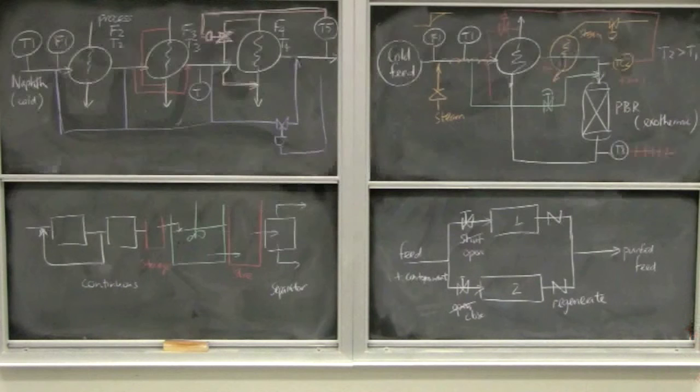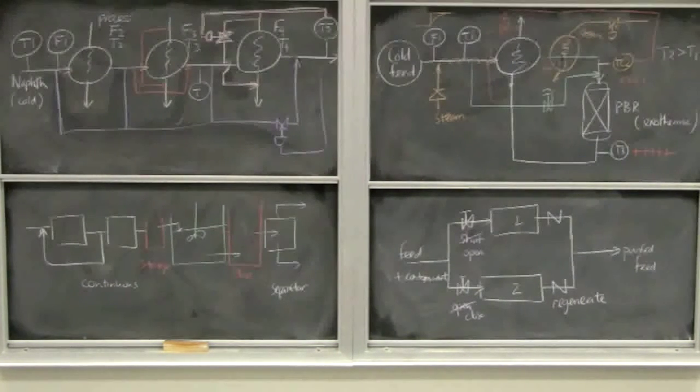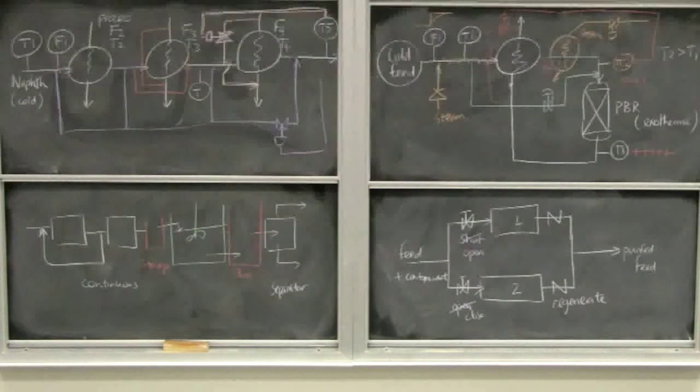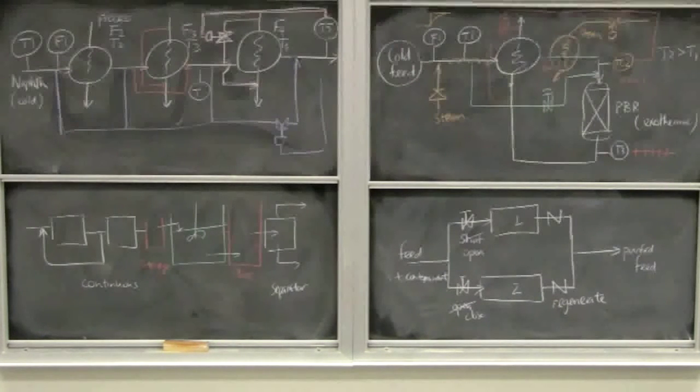So I'm adsorbing onto one bed. And then when that bed is fully loaded, so we can't put any more contaminants onto the bed anymore, I would close this valve over here and then open that valve and then use bed one. And then while bed one is being operated, I regenerate bed two. So typically, regeneration is done by running steam through the bed or you heat the bed up in some way to desorb the contaminants and you deal with the contaminants elsewhere. So we're always alternating then between the two beds in that way. There's an example, again, of transition that's added to a process. The process is going to transition from one bed to the other bed.